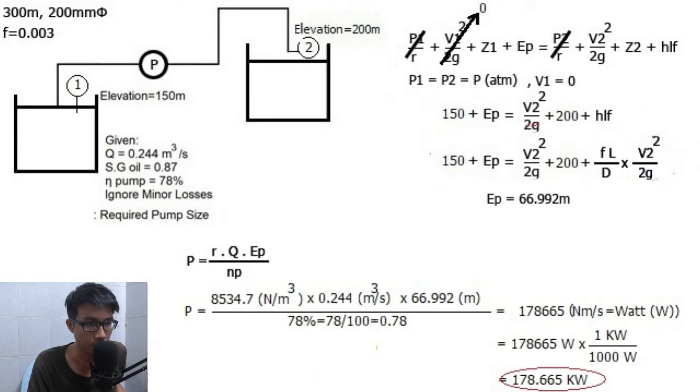Now we substitute the data in the power pump equation and we get 178.665 kilowatts for power of the pump. Power of the pump is also the same as the pump size. In this calculation, I converted 178.665 kilowatts. One kilowatt is equal to 1000 watts. Now we finish the pump sizing calculation.